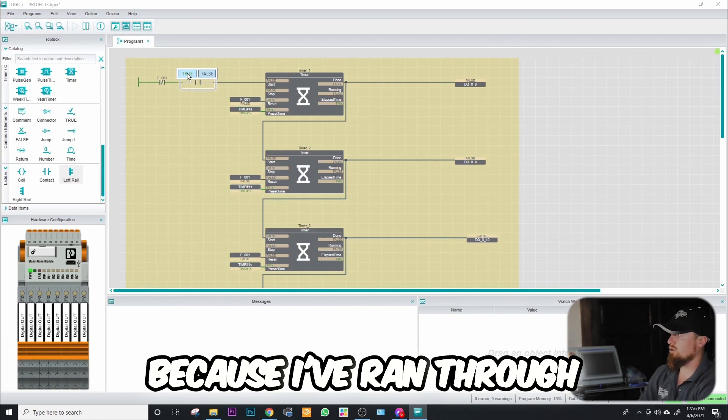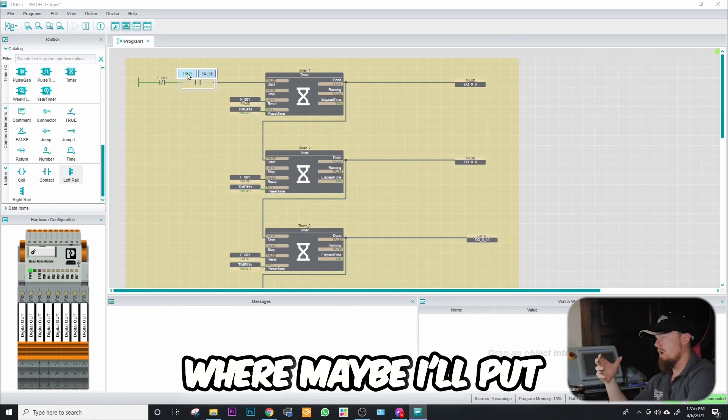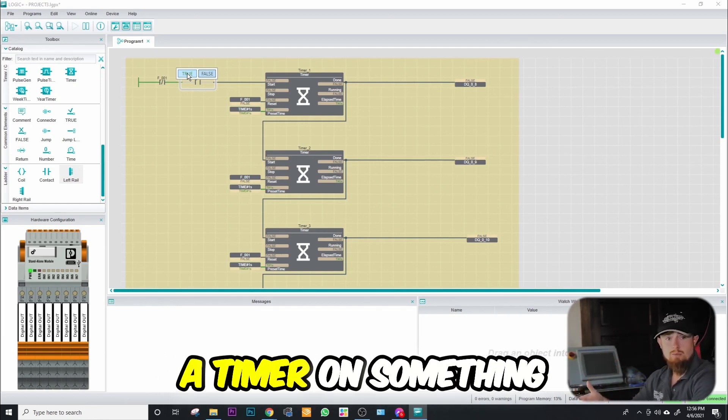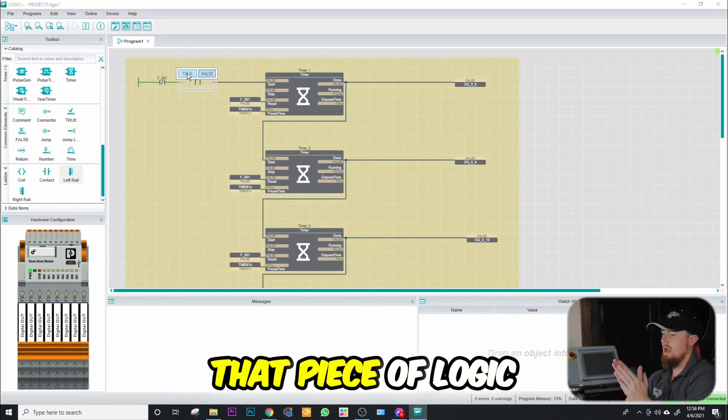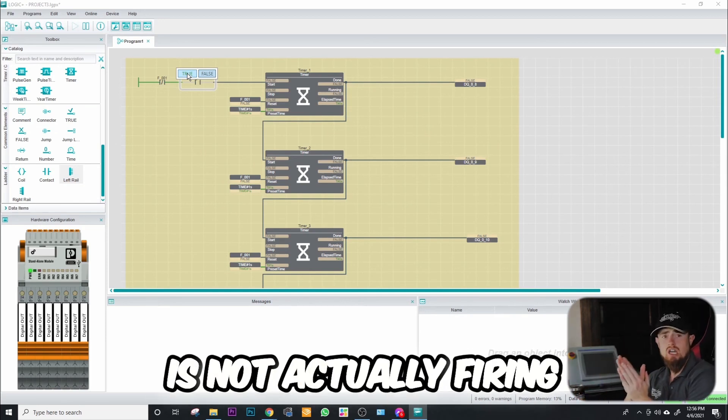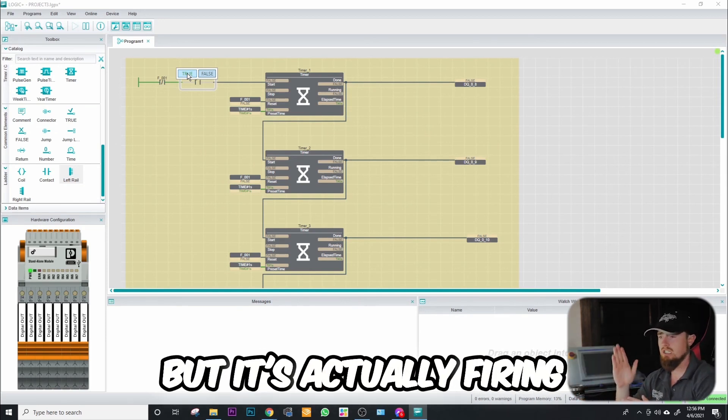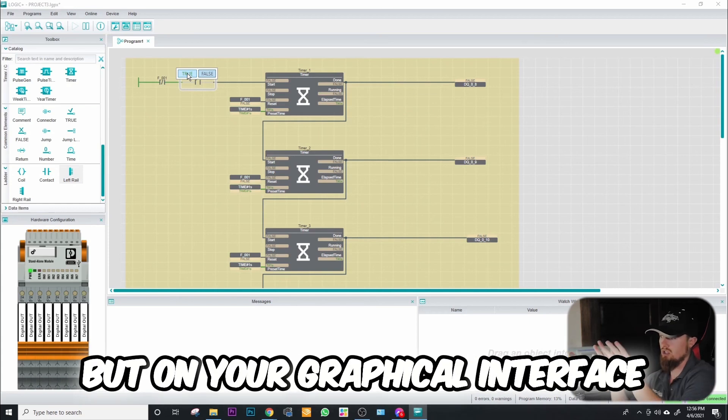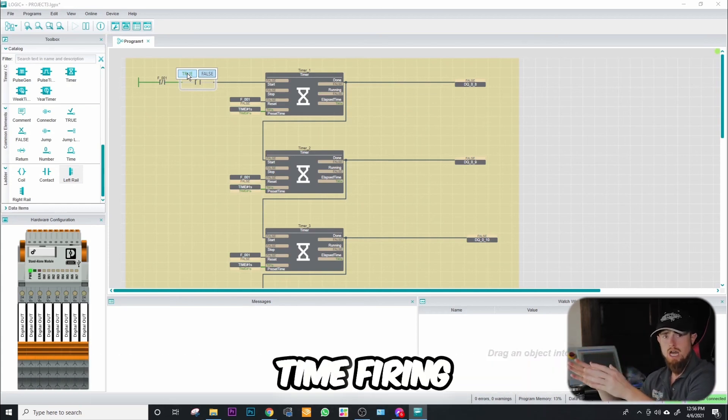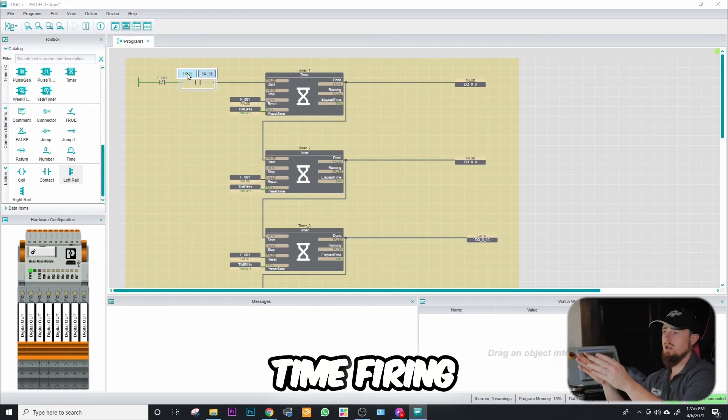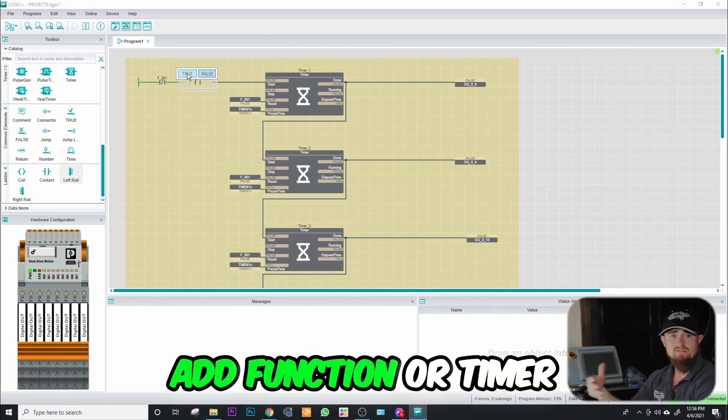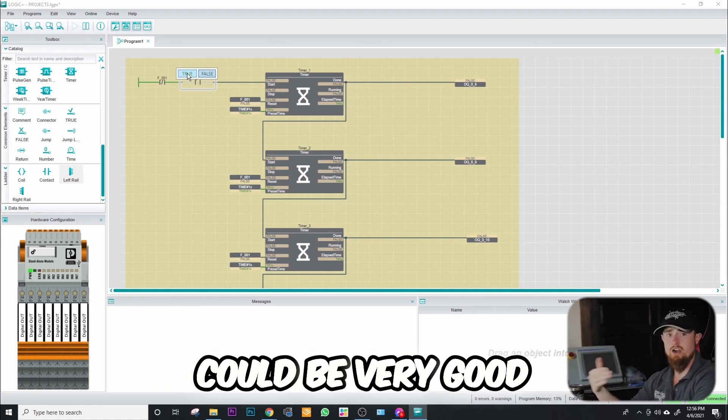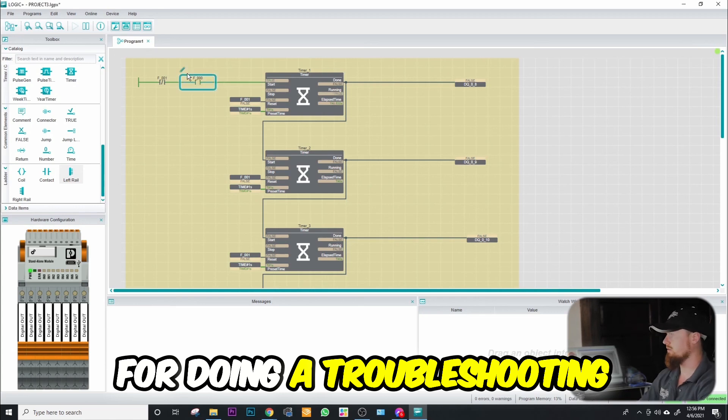I've run through times in programming code where maybe I'll put a timer on something and you'll notice that that piece of logic is not actually firing one time, but it's actually firing like six times. But on your graphical interface, it's only showing one time firing. So something like an add function or a timer could be very good for troubleshooting.